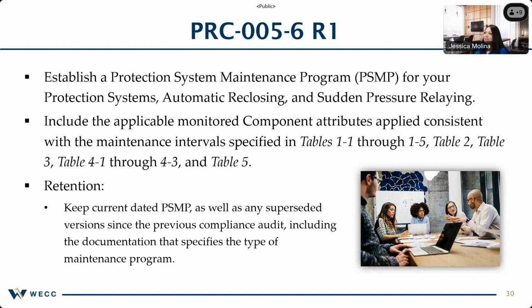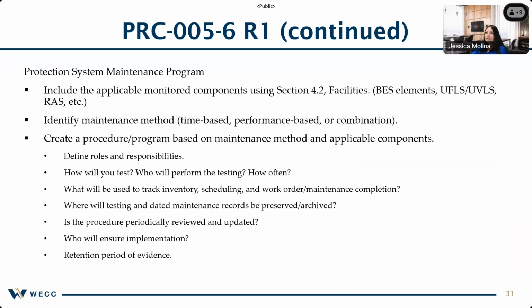Alrighty. R1 states that each TO, GO, and DP should establish a protection system maintenance program, also known as a PSMP. This program should include applicable component attributes specified in the maintenance interval tables listed in the standard. Make sure to keep a current updated PSMP as well as any superseded versions from the previous audit. Next slide, please. So creating a PSMP goes back to building a strong compliance program. You should be illustrating what you'll do and how you'll do it, define roles and responsibilities, explain how you'll test your equipment, who will perform the testing, and how often. You want to be sure to track your inventory, maintenance, scheduling, and work completion. We suggest dated documentation to help track maintenance, as PRC-005 provides maintenance activity interval tables, and I'll cover this in R3. You'll want to archive your documentation and retain it in accordance with the standard, and keep in mind that your PSMP should be periodically reviewed and updated because procedures may change over time. Next slide, please.